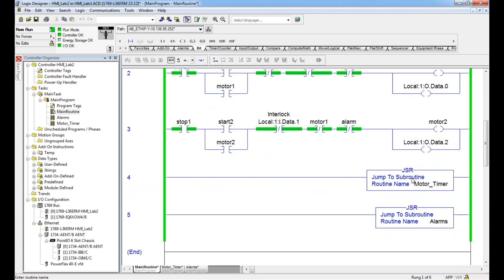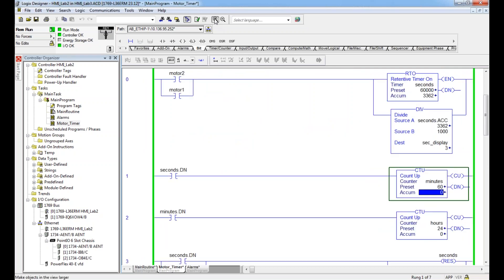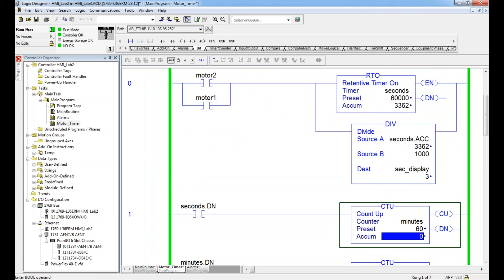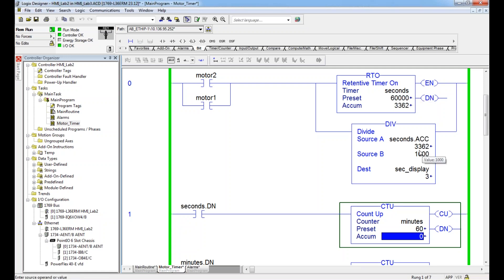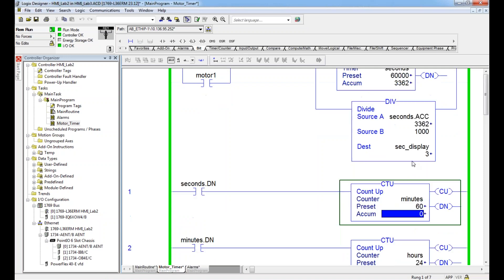Two jump to subroutines, so two JSRs - one dealing with a motor timer, one dealing with alarms. Then we go to the motor timer. Let me zoom this. Basically all I'm doing is tracking whenever the motor is running, it's going to keep track of its time. And I have a timer called seconds, and I'm just dividing by a thousand, because remember a timer in Allen-Bradley is a millisecond.